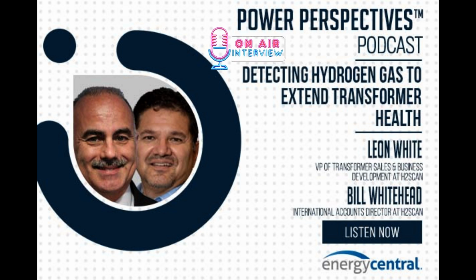With online monitoring, you're looking at the real-time health of the unit and communicating that data back remotely. Not only are you protecting your employees from being around equipment that may have issues, but you're also protecting the public and your resources by looking at the online data to see if there's a problem, and then changing out or doing maintenance on the transformer on a scheduled basis versus waiting for it to fail.